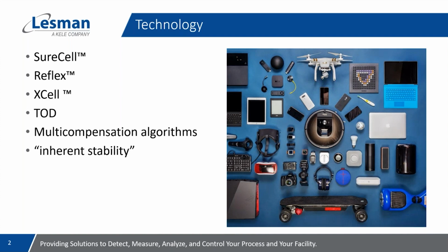Why? Why isn't there a simple answer on how frequently I should calibrate my sensor? It is the number one question I get from people who are responsible for gas systems. With all the technology out there, can't they figure out a way to minimize or eliminate the need for calibrating and maintaining my system? Or my favorite question, how often do I need to calibrate these things? My quality program says I have to follow manufacturer recommendations. What are they? The quick answer is that no manufacturer is going to answer that question directly or concisely, and there's a good reason they can't.